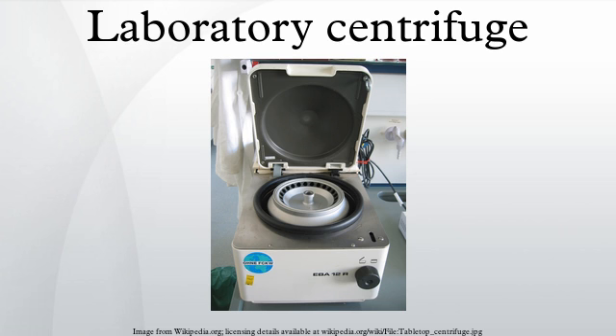Rotor failure, caused by mechanical stress from the high forces imparted by the motor, can occur due to manufacturing defects, routine wear and tear, or improper use and maintenance. Such a failure can be catastrophic, especially with larger centrifuges, and generally results in total destruction of the centrifuge. While centrifuges generally have safety shielding to contain these failures, such shielding may be inadequate, especially in older models, or the entire centrifuge unit may be propelled from its position, resulting in damage to nearby personnel and equipment. Uncontained rotor failures have shattered laboratory windows and destroyed refrigerators and cabinetry.